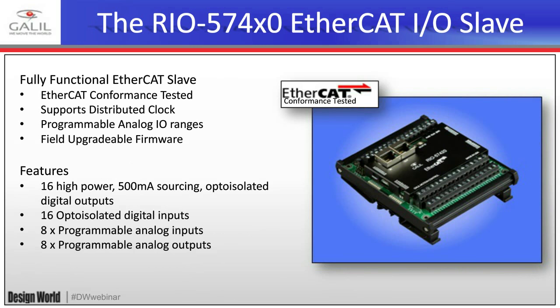Galil recently released the EtherCAT I/O module — the RIO 57,000 — which is an EtherCAT slave that communicates with the DMC-50,000 or any other certified EtherCAT master. It has been conformance tested by Beckhoff, confirming it functions as specified with EtherCAT masters. It supports distributed clock. Analog I/O ranges are programmable from 0–5V to plus or minus 10 volts. It comes with field-upgradable firmware downloadable from the Galil website. All RIOs come standard with 16 high-power 500mA sourcing opto-isolated digital outputs, 16 opto-isolated digital inputs, and an option for eight analog inputs and eight analog outputs.